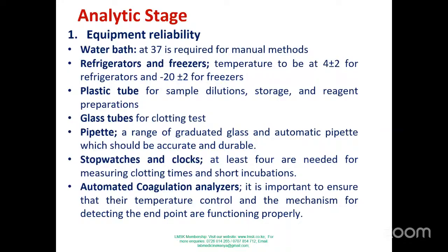And then refrigerators and freezers: temperatures to be at 4 plus or minus 2 for refrigerators. But for freezers, you maintain at -20 plus or minus 2, especially where you are going to store your citrated plasma for later use.